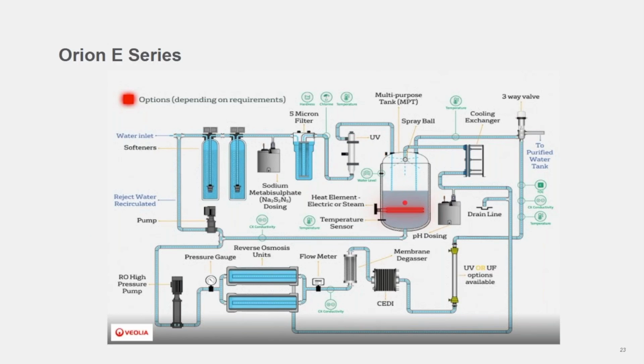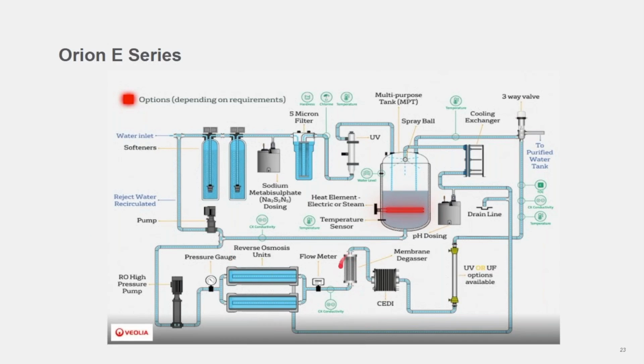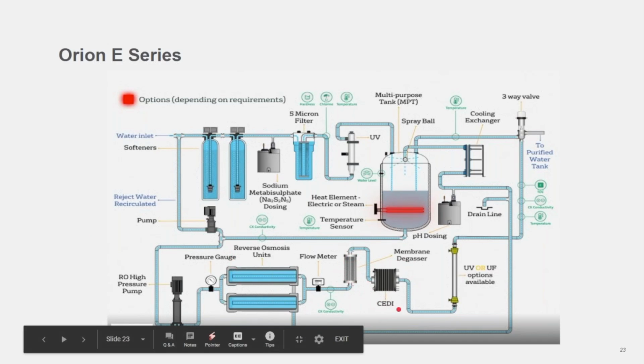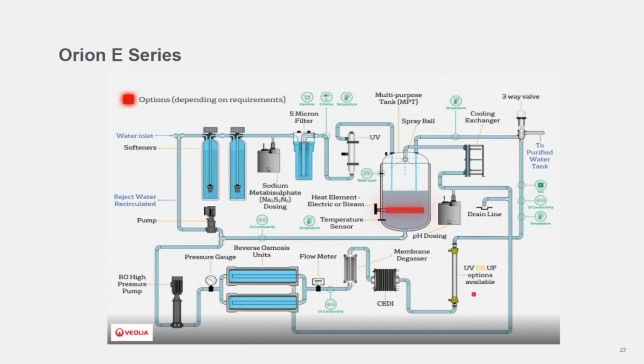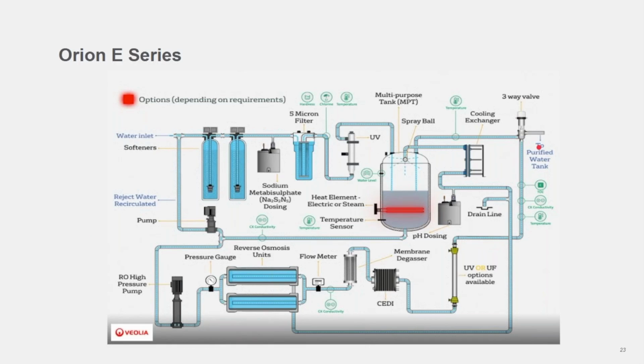And if we go further down after the RO, we have the option of a degassing membrane between the RO and the EDI. And this is there to remove any prevailing CO2, depending what's in your raw water, to protect the EDI unit. And then after the EDI unit, there's 2 options of either a UV or a UF, and the UF for cold WFI to remove any prevailing endotoxins. And then you again go up and fill the purified water tank via the 3-way valve at the top there.